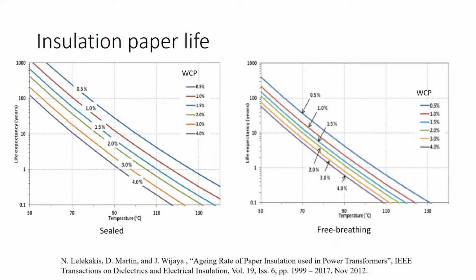Chances are that they're not usually sealed, they're just free breathing, and then the air can actually get into the tank. The WCP there just refers to the water content of the paper. So this is just showing that as the transformer insulation becomes wet, its life expectancy falls.